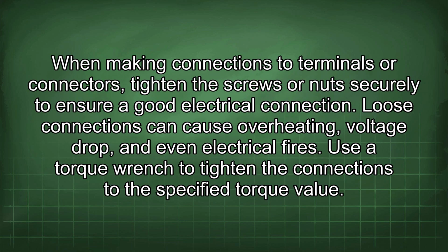When making connections to terminals or connectors, tighten the screws or nuts securely to ensure a good electrical connection. Loose connections can cause overheating, voltage drop, and even electrical fires. Use a torque wrench to tighten the connections to the specified torque value.